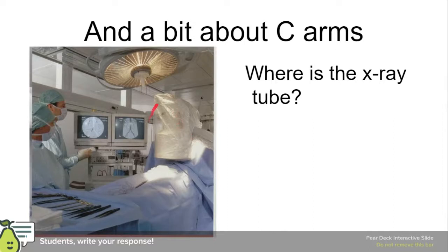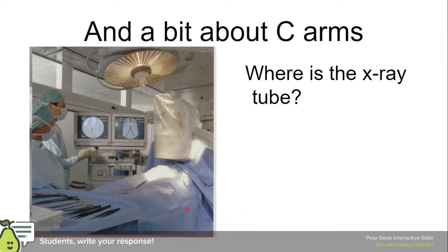All right, there's a plastic bag over it. This is a sterile bag. Now, the surge tech or the scrub nurse who's already scrubbed in is the one who's actually going to start putting this over the C-arm, over the image intensifier part. And you're going to assist in making sure that it's pulled down and is covering the C part, which basically is going to come underneath here, go down, and be underneath the table. Because remember, the source of the X-rays has to hit the image intensifier. So basically, it's going to be way down here. All right. So that's going to be underneath.